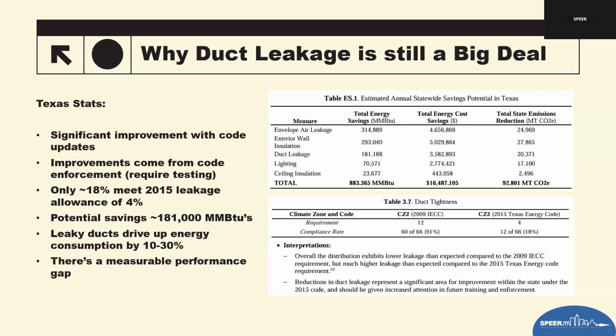The table on the right shows an estimated statewide savings potential. Duct leakage alone represents about 181,000 MMBTUs of potential savings every year in Texas if we've got those ducts tightened up. That's the third highest savings opportunity out of all the measures that were studied. And remember, leaky ductwork directly drives up energy consumption. Even national studies consistently show that duct leakage can waste anywhere from 10 to 30% of the home's heating and cooling energy. Of course, in Texas, we have hot, humid attics for the most part, and those losses are even worse.